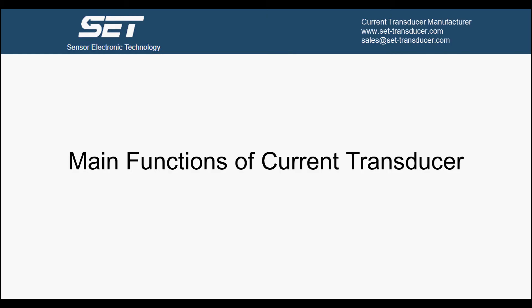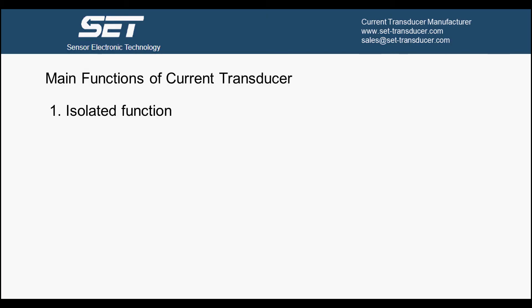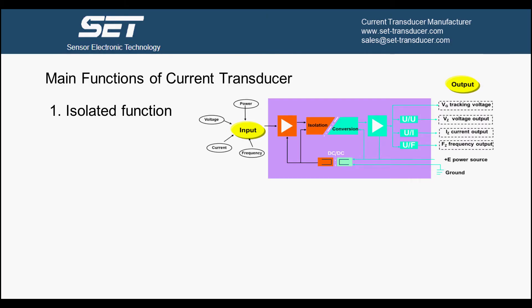The last thing is why it is so important to use current transducer in many different industry systems. First: isolated function. In the design of current transducer, the input current is absolutely isolated from output current. As in the industry environment, there are a lot of interferences which cause measurement signals to be inaccurate. Using current transducer can get rid of the interferences, so the output signal can fully represent the measured signal.